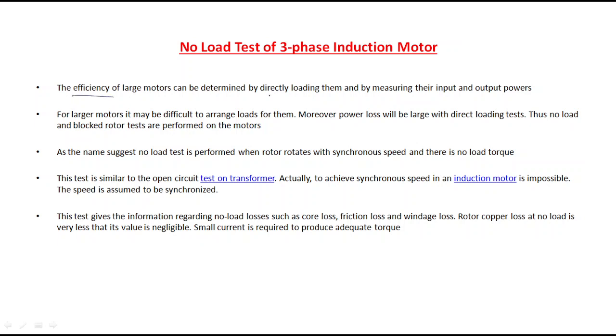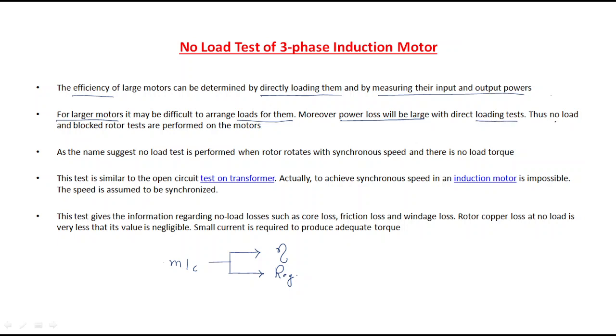The efficiency of large motors can be determined by direct loading, by measuring input and output powers. For any machine, two things are important to understand performance: efficiency and regulation. For large motors, it may be difficult to arrange loads, and power loss will be large by direct loading. If you are using a high load, the power loss is also very high.